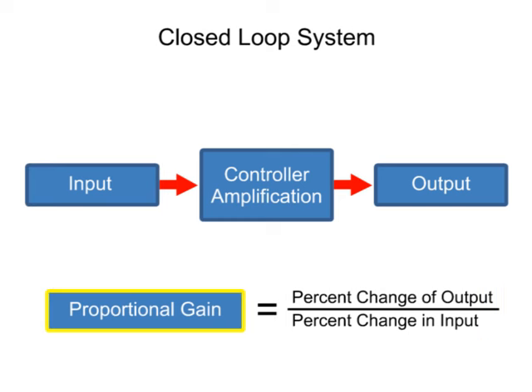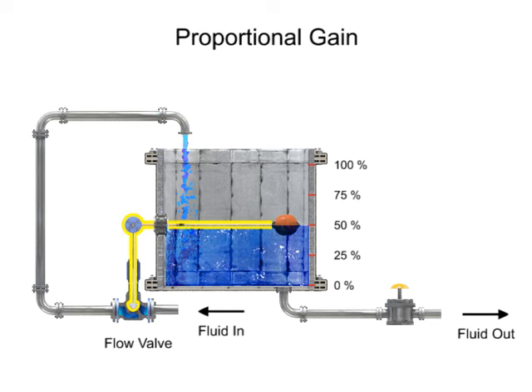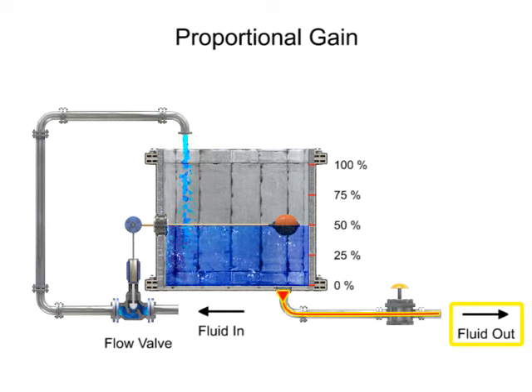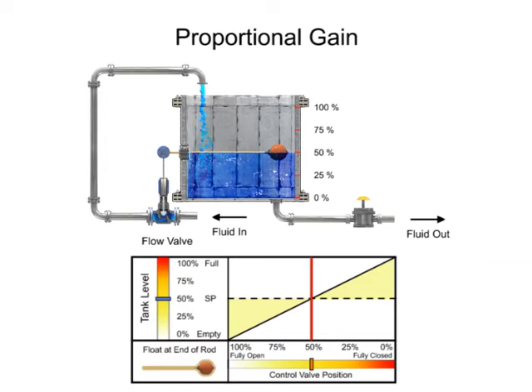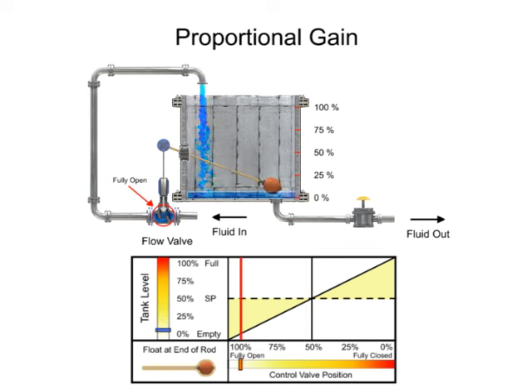To illustrate the concept of gain, a common process of regulating the level of fluid in a tank with a float attached to a control valve is used. The float mechanism is designed so that when the tank level is half-full, the flow valve is open to the position that causes the amount of fluid entering the tank to equal the amount leaving. The float on the end of the rod is positioned to meet the minimum and maximum flow capability of the valve. The valve is actuated by the float to a fully open position when the tank level is low, and fully closed when the tank level is full.